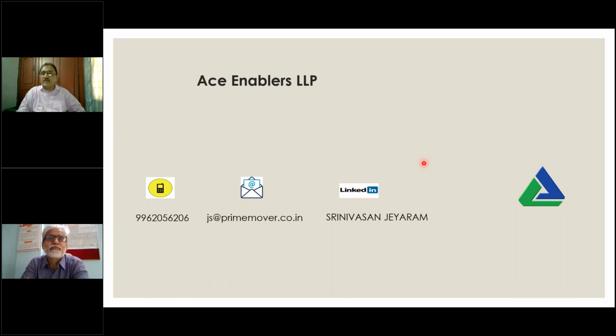Yes, yes. In Tamil Nadu, it is penalty. Many people have been forced to take action. But wherever it is kVAH billing, if the effect of harmonic distortion is not included, I would imagine people will continue to do business as usual. But if it is also included in the trivector meter, we will have to be very careful about managing the kVAH billing. In Maharashtra, kVAH billing is only for the HT consumers, and even there harmonics is not included. For LT it is still kWh, but there the power factor is there, no harmonics. But for HT it is kVAH billing. That means indirectly the power factor. They won't tell you to reduce the kVAH if the gap is high. They will happily take the payment from you. So in our own interest, we'll have to do this exercise of reducing.